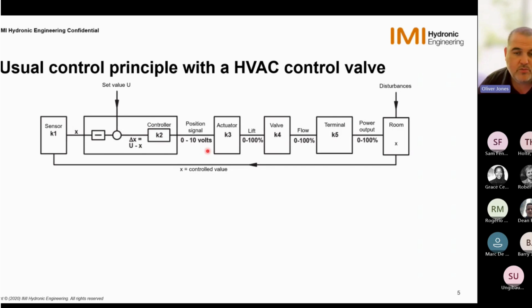The position signal, which is communicated to the actuator, will position itself according to the voltage supplied. So 0 volts would be closed typically. The design position would be 10 volts, and 50%, 5 volts would be open. Sorry, 50% of the valve open at 5 volts on a standard linear 2-port control valve.